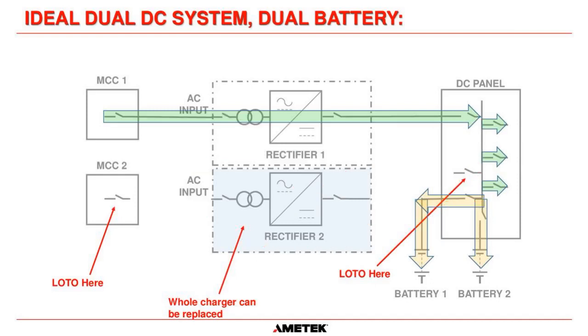Marcos is asking how to avoid that one battery feeds back to the other battery. In truth, it's not an issue unless there is a fault, and then you can put fuses that could clear a fault in one battery that would allow the other battery to feed into it. In truth, you could also have some kind of diode arrangement if you wanted to, but I don't think there is a need for that. I just think you should connect two batteries in parallel through their own disconnects, and you will be fine. Once again, that's my opinion.